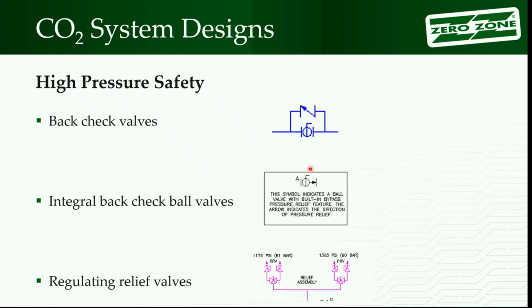So that's out there. Otherwise, there's another brand of valves out there that has an integral check valve built into it. You won't see something piped around the outside of it, it's all built into the body. It's the same premise. If I close the valve and the pressure builds up here, instead of rupturing the pipe, it bleeds through the valve body itself and lets the pressure go down. So those are two items that can be used to help maintain or prevent an overpressurization in the system.